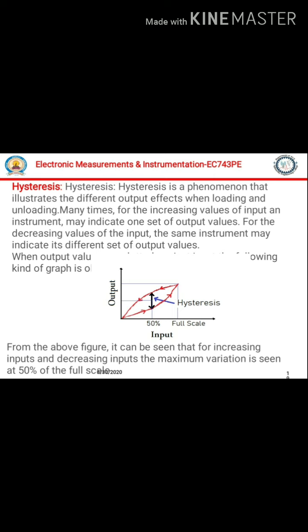So this process of differing in both directions, the performance of the instrument in both directions changing, is called hysteresis. This happens because of the internal electrical, mechanical, and magnetic effects, whatever components you are using. Basically, more magnetic elements cause more hysteresis, and based on certain components, this hysteresis occurs in the performance of an instrument. For better performance, hysteresis must be low.